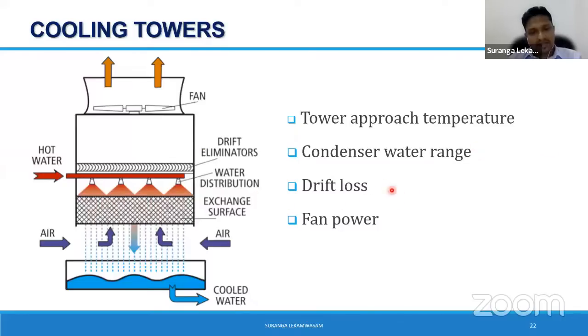Then drift loss. That is again important. When you run the fan, due to the air stream, not the evaporation, water droplets can be taken out by the air stream. This is not the evaporation, right? Evaporation happens anyway. Some water in the water phase, water droplets, can be taken out. That is a loss. That is called drift loss. So you have to minimize that, probably with drift eliminators or with the construction. Typically, we say it should be less than 0.01% of the condenser water circulation. That should be in that range.